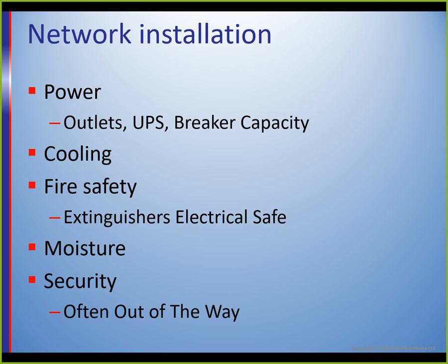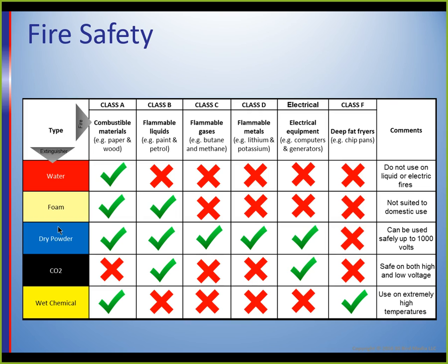Moisture, humidity, can be an issue, and after a while you get a little bit of corrosion on some of the wiring, some of the plugs. When you think about the low level of signal voltage, it doesn't take a whole lot of corrosion to interfere with that. So moisture, dehumidifiers, moisture level as well as temperature level become important for these things. And the cooling, the temperature level, one of the things that I've heard for a lot of years is that if you're comfortable, your equipment's probably comfortable. If you're uncomfortable, your equipment's going to be uncomfortable heat-wise for these things.